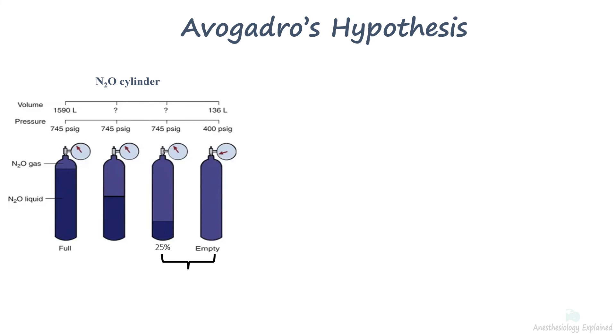The pressure will remain constant until 75% of the 1590 liters of gas is consumed, which is approximately equal to 400 liters. Prior to this point, the cylinder must be weighed to determine the amount of gas.